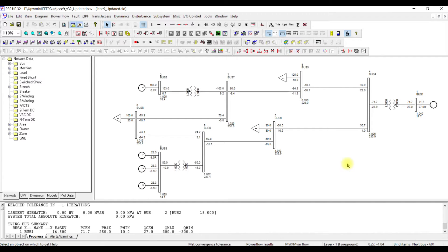Welcome to the transient stability analysis using PSS/E demonstration video. In this demonstration we are going to perform frequency stability analysis using the IEEE 9-bus system, slightly modified so that instead of one generator at bus 3 we have used 3 generators. This is to perform small steps in frequency stability, since the total unit size was around 85 MW, divided into generators of 28 MW each. This gives a smaller step size to illustrate how frequency stability works.